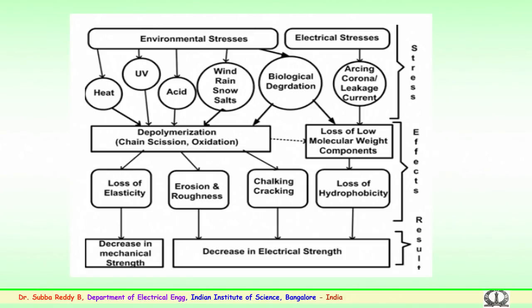Then another environmental factor is the wind. Wind brings a lot of dust and pollutants to the surface. Over a period of time this settles and the contamination builds up on the surface. In case there are some damages, these pollutants may enter the surface and slowly degradation could happen. Wind also depends on which part the insulator string is in. Because of the sand, even the sand sometimes contains very high salts. These salts are again sprayed on the surface and could damage it.